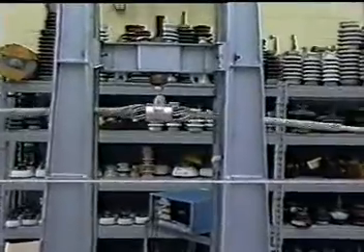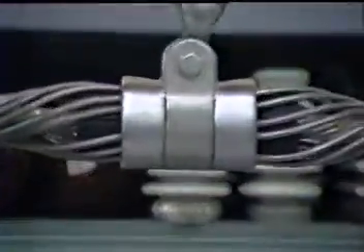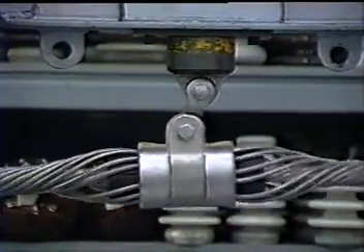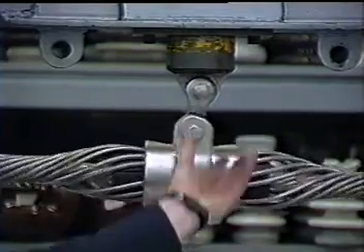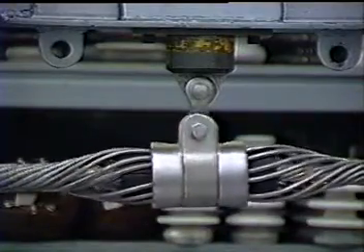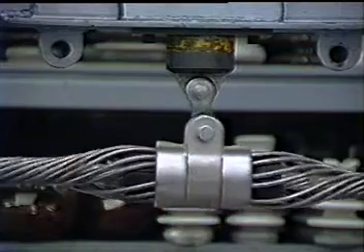You'll also hear in the background a clunking which is occurring. That is because, due to the galloping activity, the forces of gravity are being overcome and the suspension clamp is lifting up and hammering down on the hardware fitting. And this is causing a very high loading on the suspension.